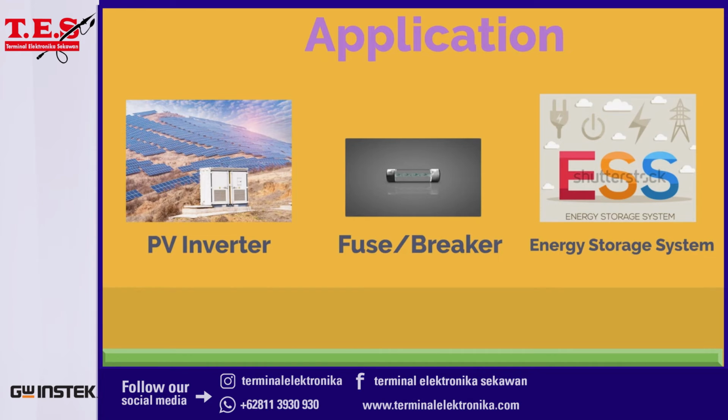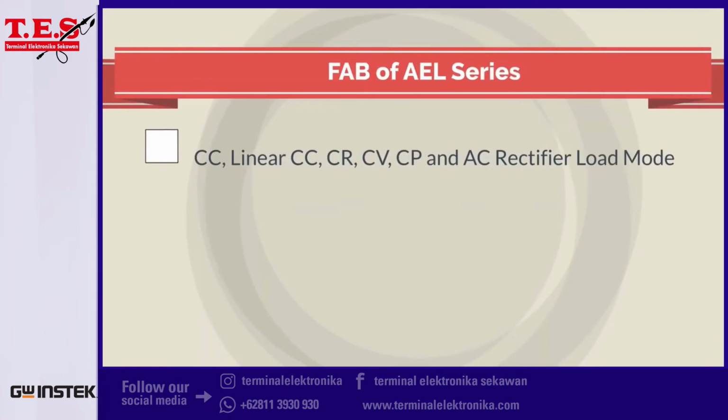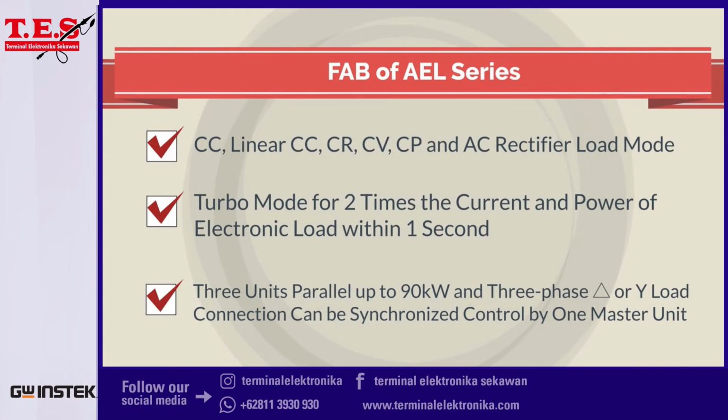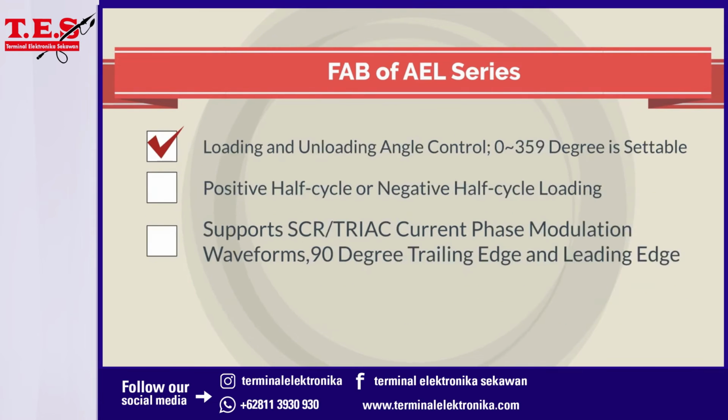and other applications. CC, linear CC, CR, CV, CP and AC rectifier load mode. Turbo mode for 2 times the current and power of electronic load within 1 second. 3 units parallel up to 90 kilowatts and 3-phase or Y load connection can be synchronized control by 1 master unit. Loading and unloading angle control, 0-359 degree is settable.